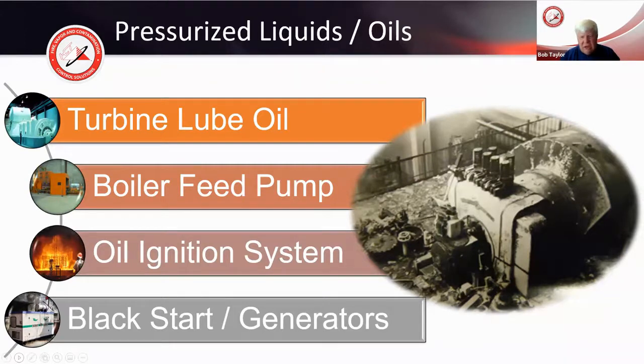So now you have running liquid, you have it under pressure, and all the things like, oh no, what do I do? Oh, you mean to tell me that that foam doesn't work? And the answer to that is yes, that is correct. Firefighting foams are not for three-dimensional scenarios. They're bubbles. They make a bubble over a surface and temporarily, for limited time only, separate the air from the fuel. They do nothing in three-dimensional. It runs right off. You can't build a blanket on a three-dimensional item.